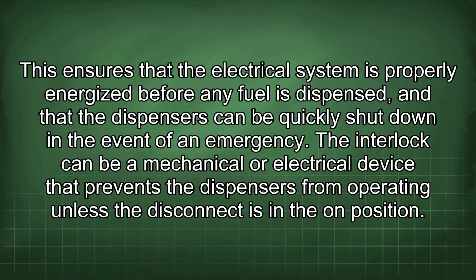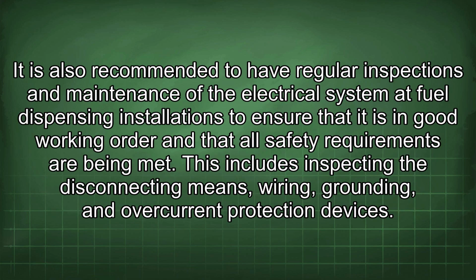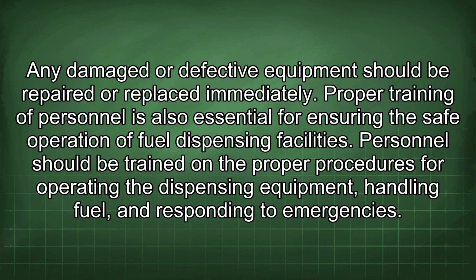The interlock can be a mechanical or electrical device that prevents the dispensers from operating unless the disconnect is in the on position. It is also recommended to have regular inspections and maintenance of the electrical system at fuel dispensing installations to ensure that it is in good working order and that all safety requirements are being met. This includes inspecting the disconnecting means, wiring, grounding, and overcurrent protection devices. Any damaged or defective equipment should be repaired or replaced immediately.